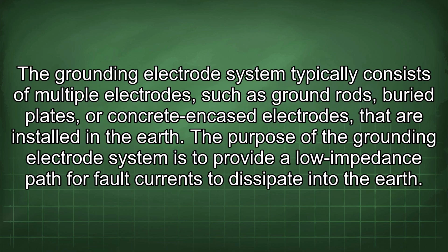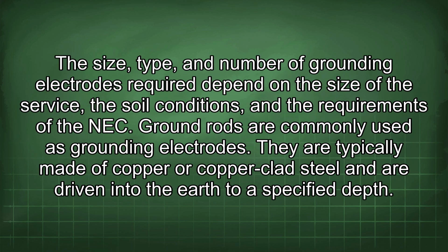The grounding electrode system typically consists of multiple electrodes, such as ground rods, buried plates, or concrete-encased electrodes that are installed in the earth. The purpose of the grounding electrode system is to provide a low impedance path for fault currents to dissipate into the earth. The size, type, and number of grounding electrodes required depend on the size of the service, the soil conditions, and the requirements of the NEC.